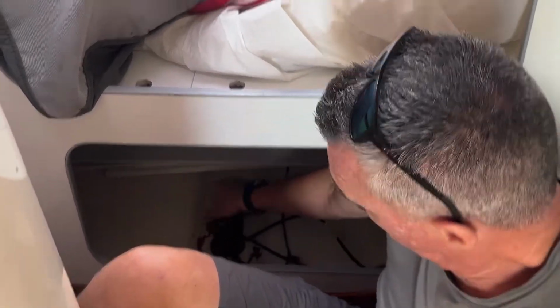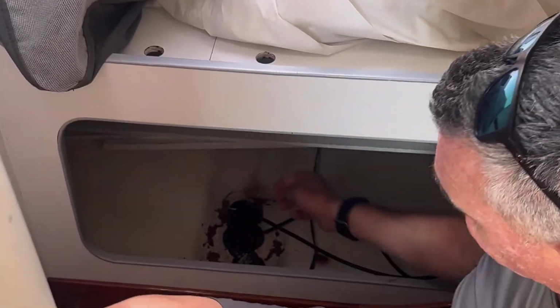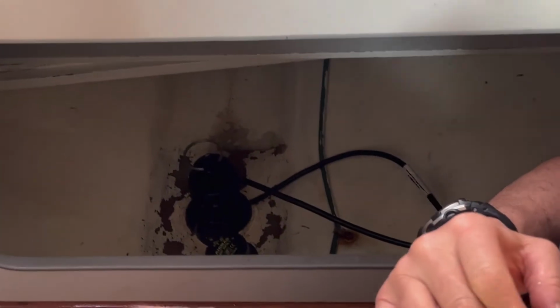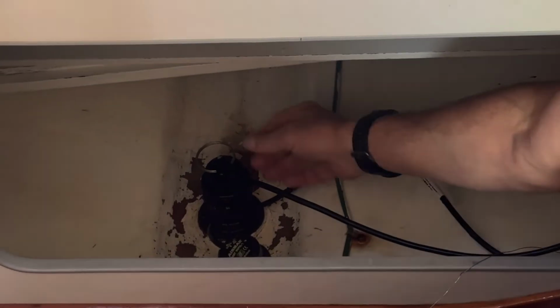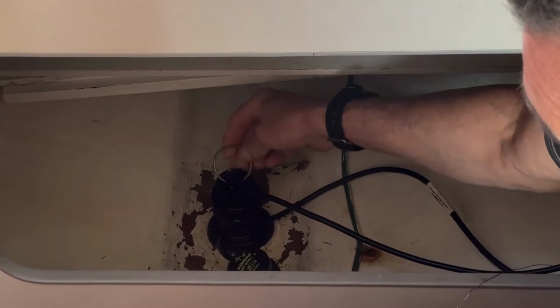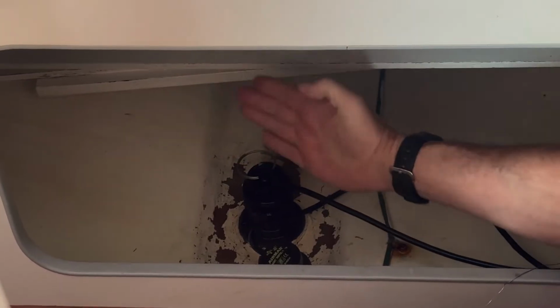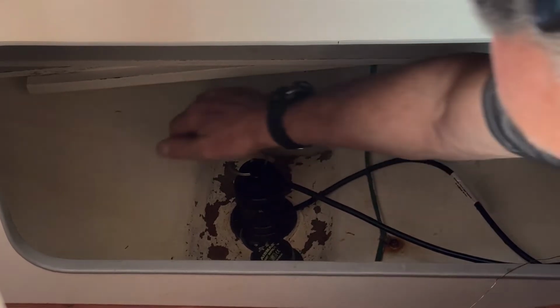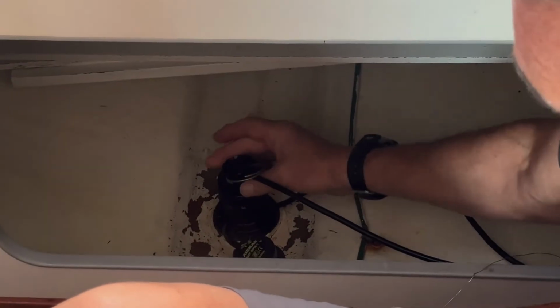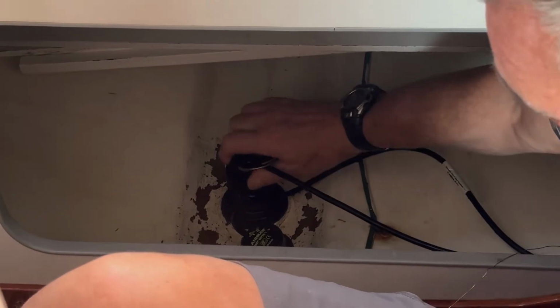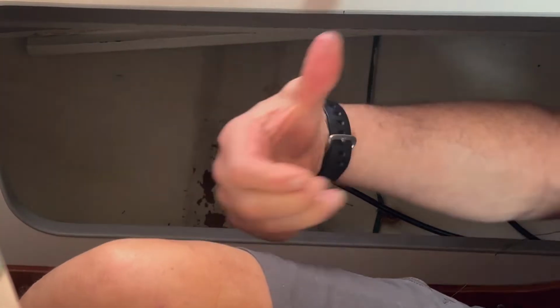What you want to do when you put the transducer in, obviously, you put the grease on the O-rings every single time. You slide the plug out, you slide the transducer in, and I put it in at an oblique angle, maybe pointing off to the left or right by 20 or 30 degrees. Push it down as far as you can, tighten the nut a little bit so you get the nut finger tight, then back the nut off like a quarter of a turn. While pressing down on it with your thumb, turn it till it lines up straight, and you'll feel and hear it click into its keyway, just like that.